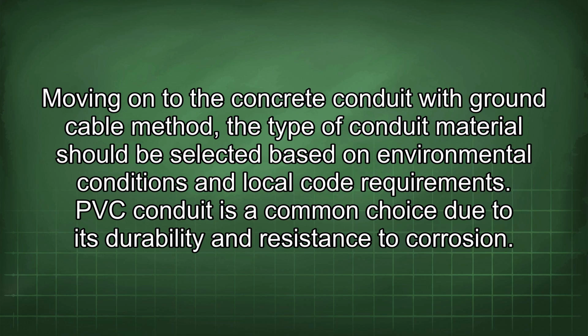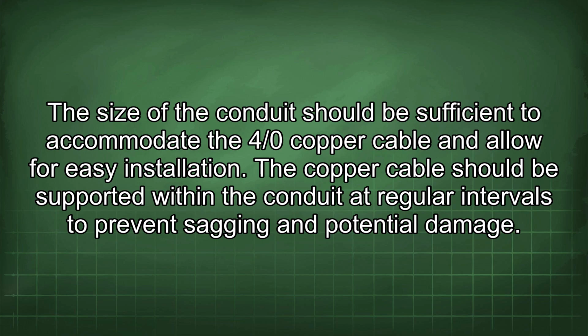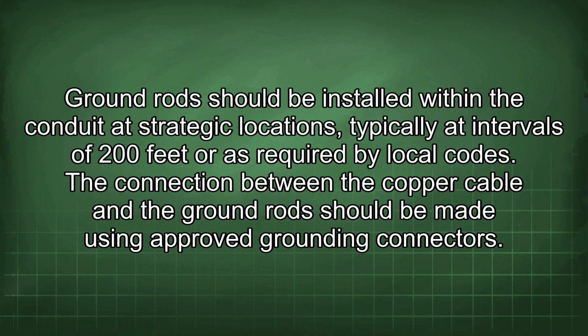Moving on to the concrete conduit with ground cable method, the type of conduit material should be selected based on environmental conditions and local code requirements. PVC conduit is a common choice due to its durability and resistance to corrosion. The size of the conduit should be sufficient to accommodate the 4/0 copper cable and allow for easy installation. The copper cable should be supported within the conduit at regular intervals to prevent sagging and potential damage. Ground rods should be installed within the conduit at strategic locations, typically at intervals of 200 feet or as required by local codes. The connection between the copper cable and the ground rod should be made using approved grounding connectors.